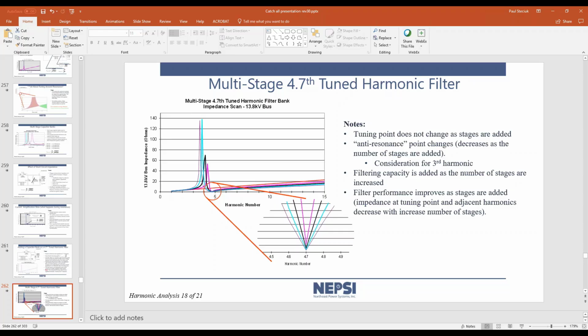So the practice in general should be always to install a fifth harmonic filter, even if there is no fifth harmonic within a network, because it only takes a small amount of fifth harmonic within a network to cause issues. If you were to install an 11th harmonic filter, for instance, there will be a resonance beneath the 11th harmonic from that filter, and that resonance could correspond to the 7th harmonic or the 5th harmonic, depending upon the network, and cause problems. So always start at the lowest frequency and work up from there. Start at the 5th, and if you need to add filters at the 7th, then do so, but you must always start at the 5th.